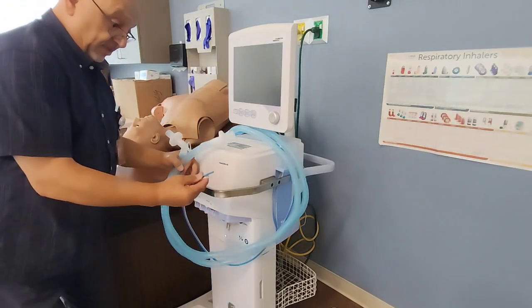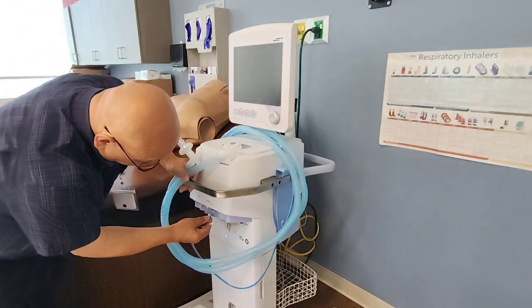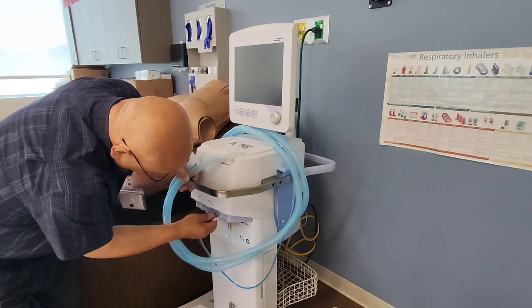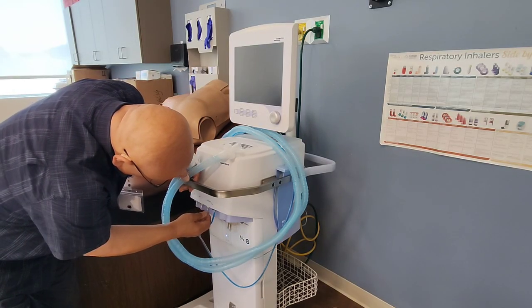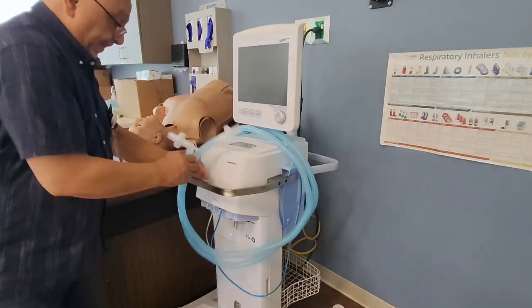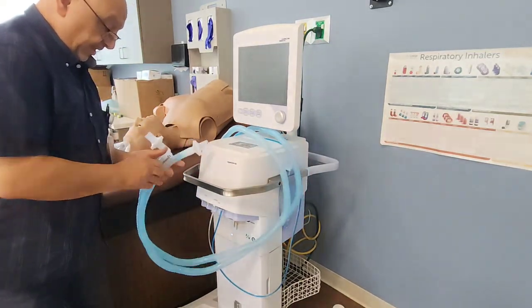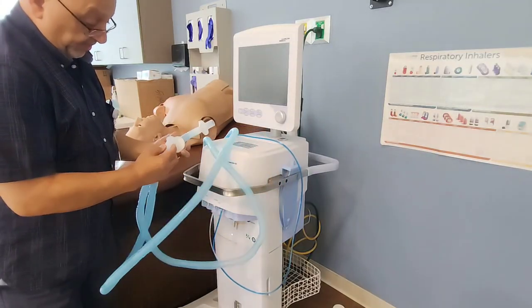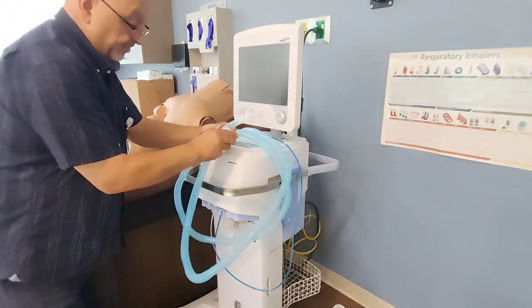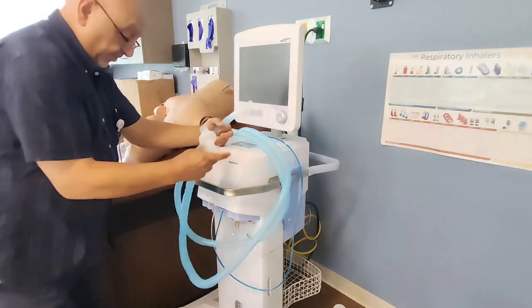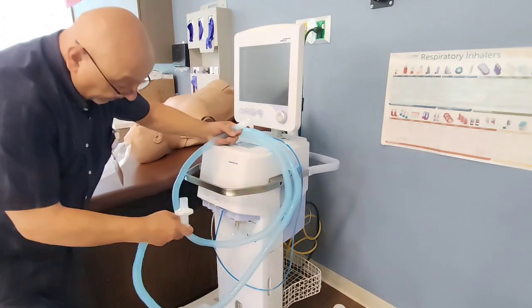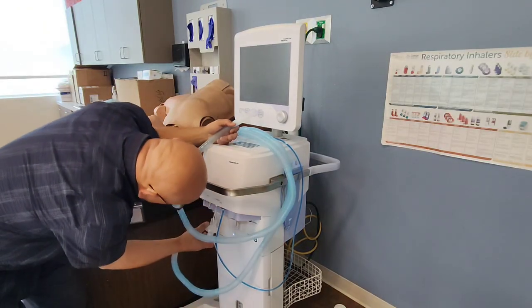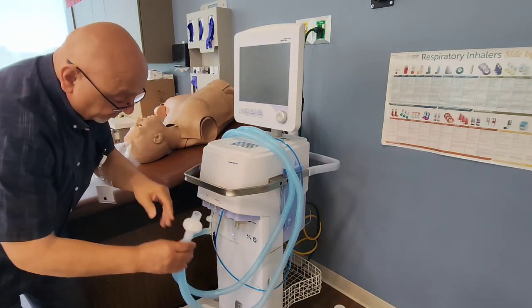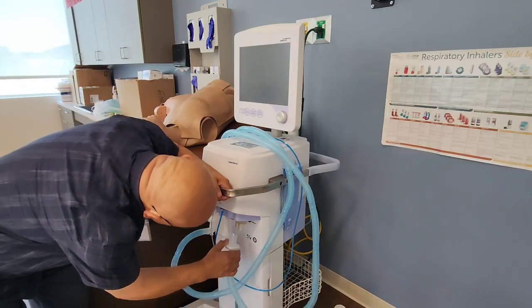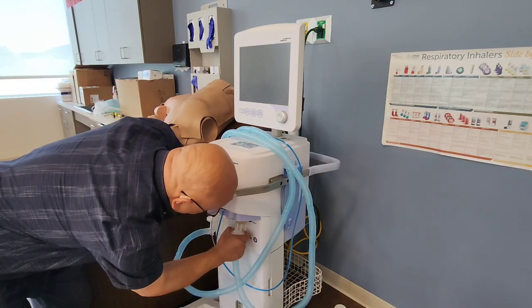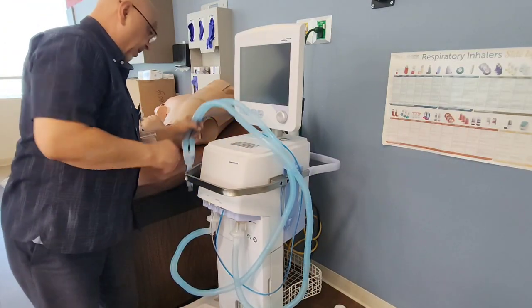Anyways, okay, so we have the flow sensor line. Just match the color, blue on blue, to the patient, and the flow sensor, the clear one on the clear. Again, remember which is the inspiratory one. Be careful, make sure all your lines are connected, nothing has come apart. That's one thing you need to do. This goes to the inspiratory, going to the patient, and that is over here on the far left. This other bacteria filter goes to the exhalation from patient. Okay, and we're all set here.